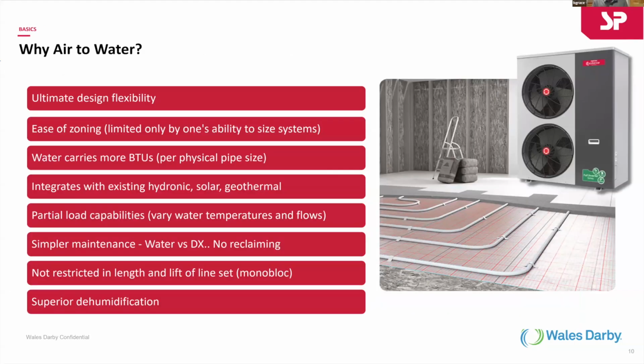Okay. So why air to water? Well, the ultimate is that it gives you tremendous design flexibility. And obviously that's really important for you guys. You're out to design houses that are optimum in efficiency, but in the bottom line, you want them to be aesthetically clean and aesthetically nice. And you also want them to be comfortable, because that's the main part of a home, making a house comfortable. So with air to water, the beauty is you have the flexibility of hydronic heating. Hydronic heating allows for ease of zoning. It also, for the amount of BTUs water carries compared to running ductwork, takes a lot less room.